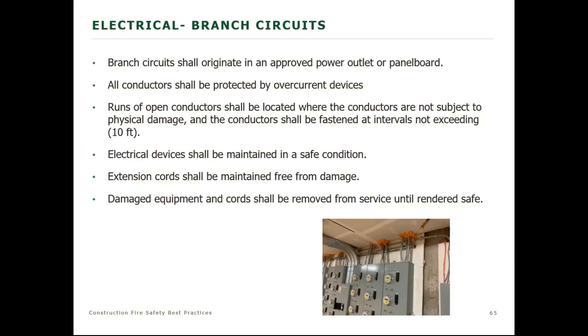Electrical devices should be maintained in a safe condition. Extension cords shall be maintained free of damage. How many times on a construction site do you see extension cords that have been cut and they just tape them up because they don't want to pay $80 for an extension cord? Any kind of damaged equipment should be removed from service until it's fixed or replaced. But they do have codes that govern temporary electric.